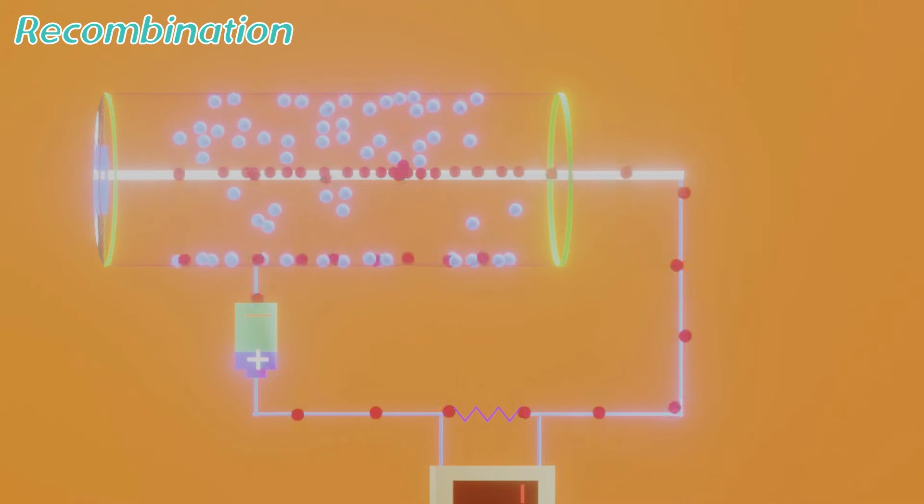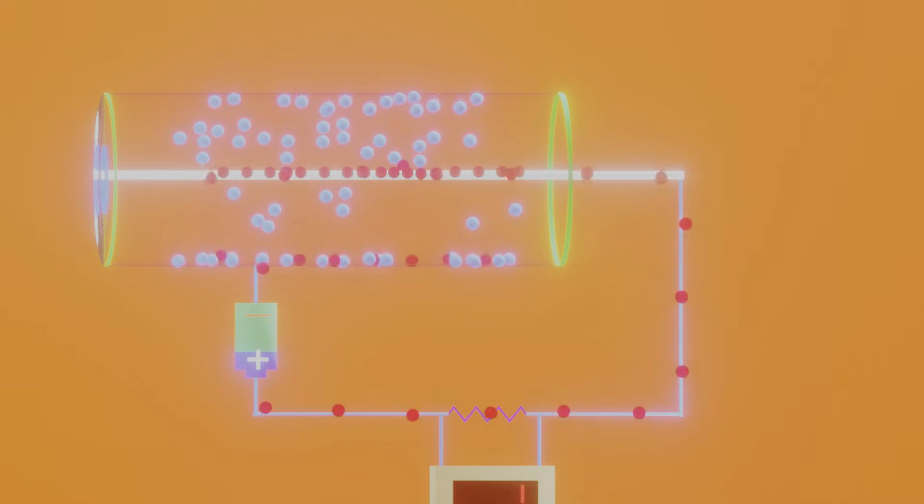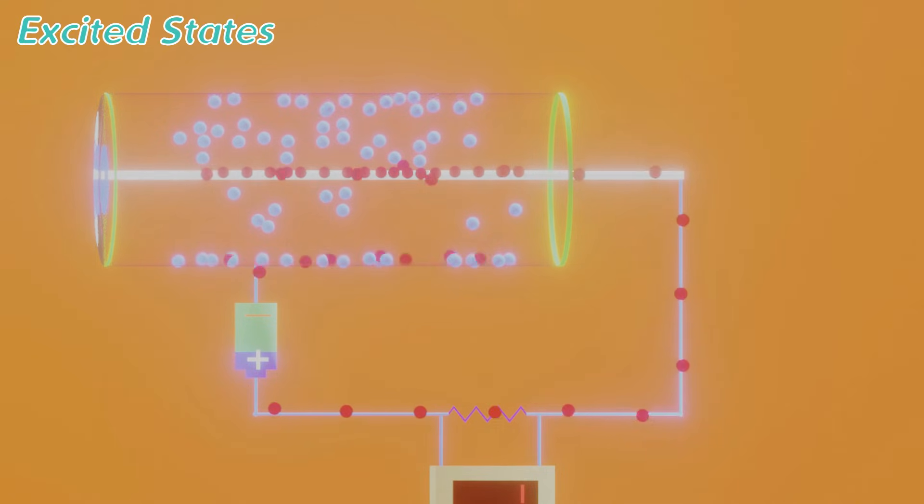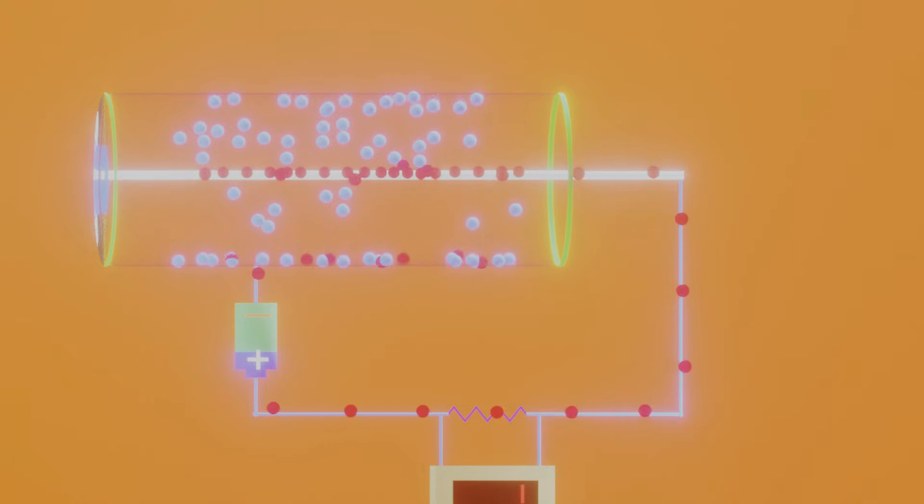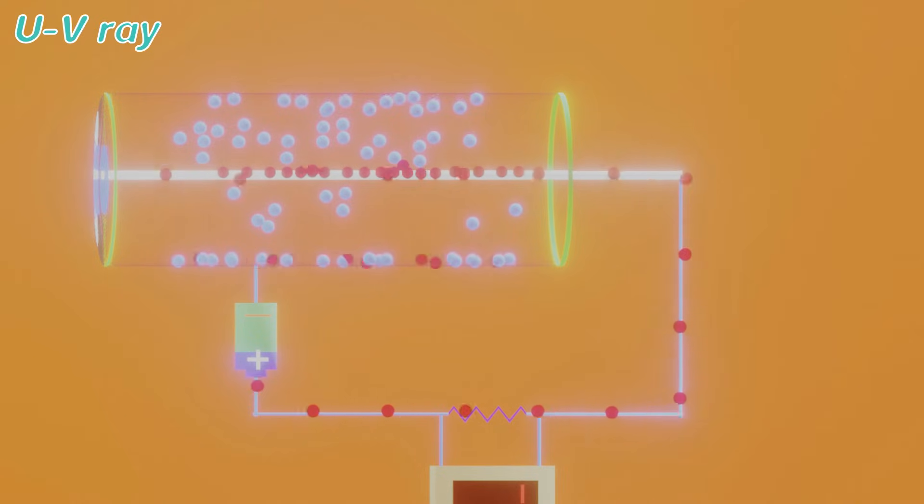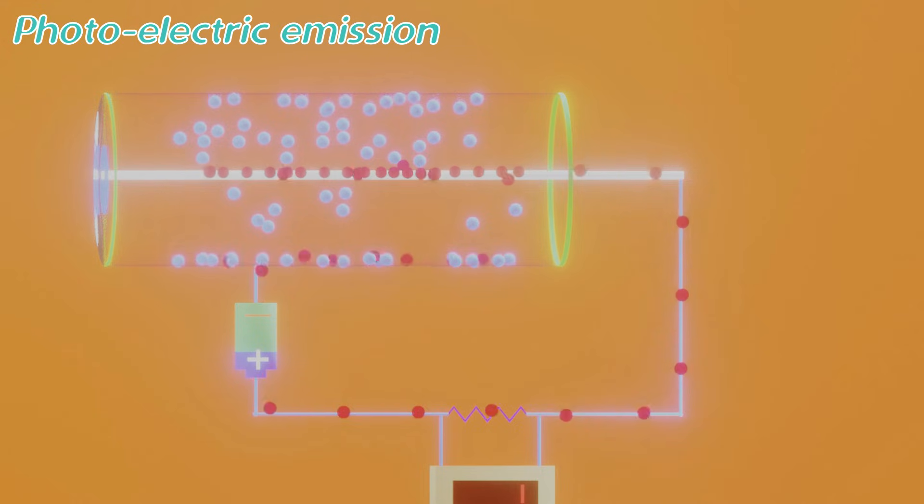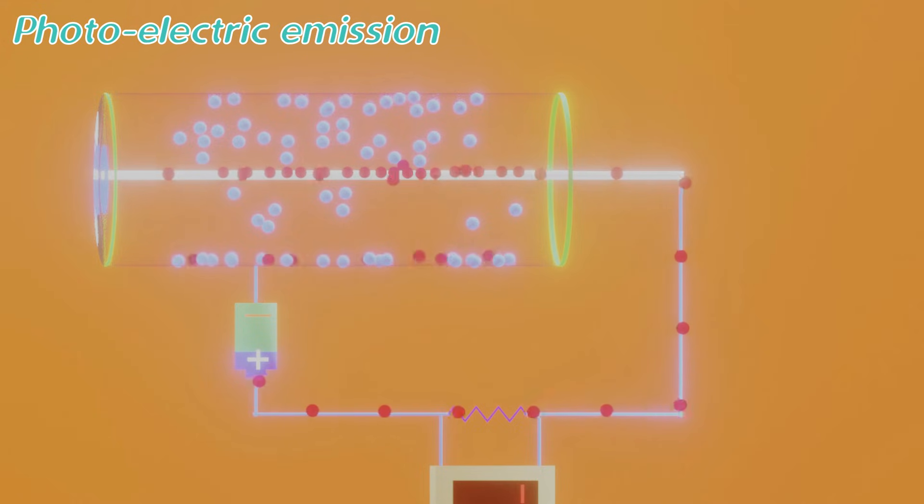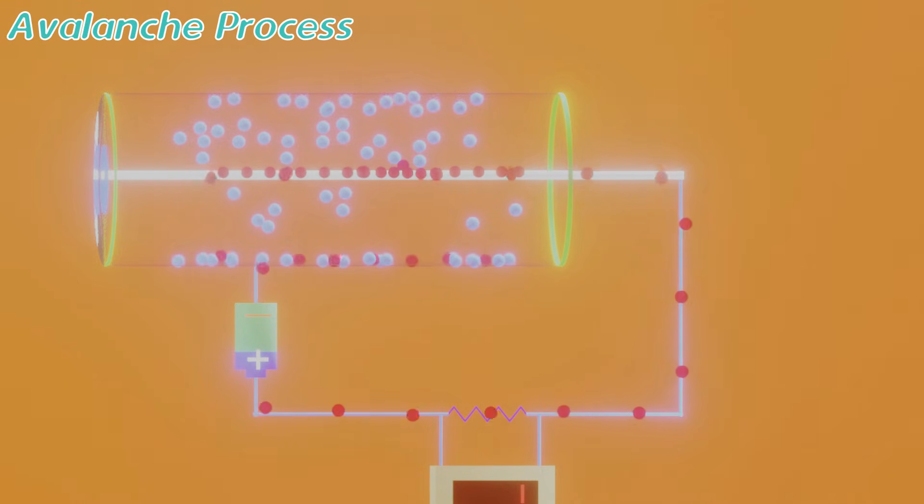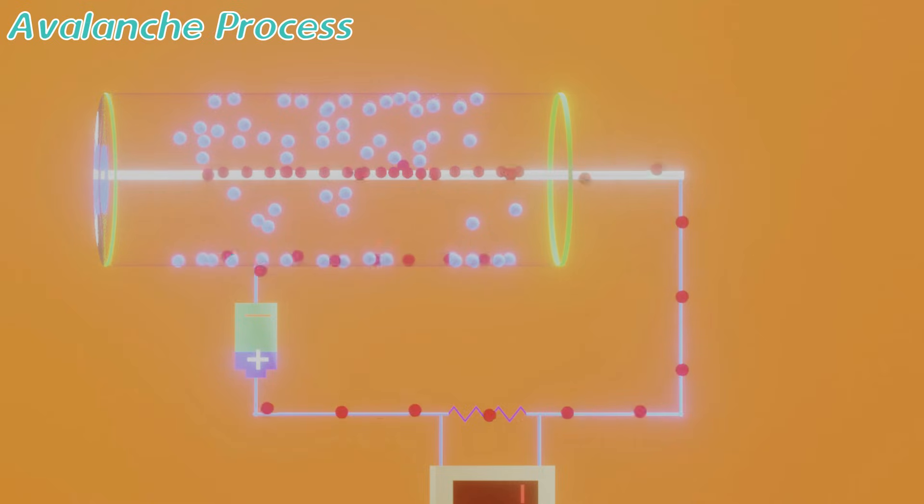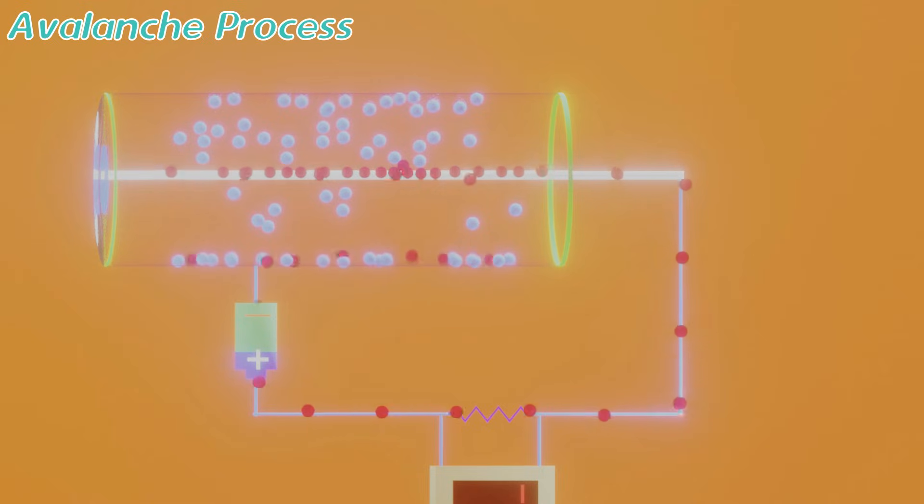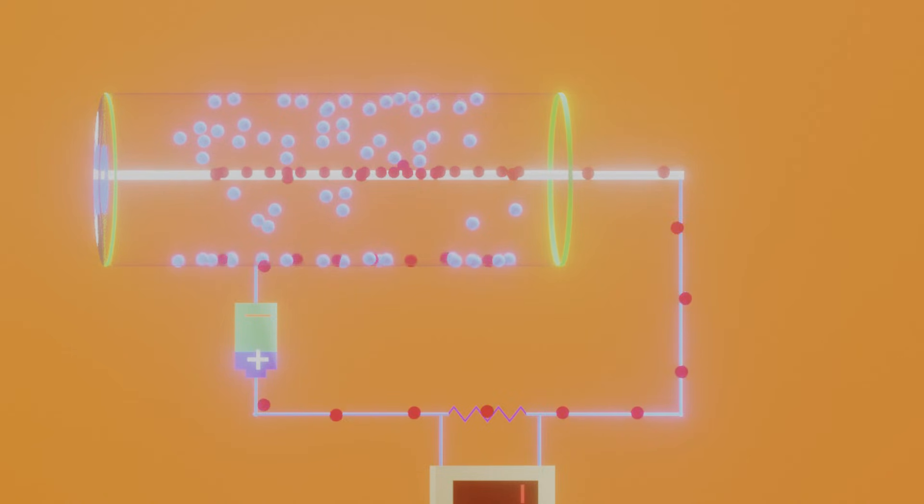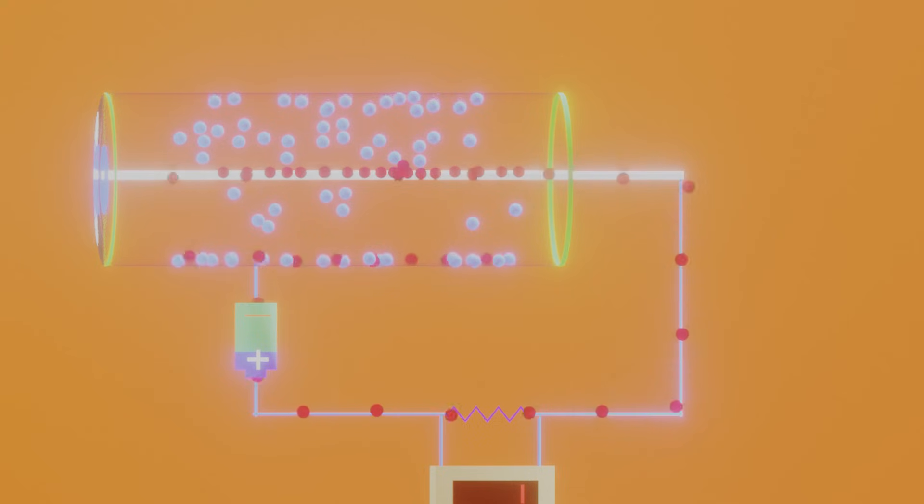When the recombination occurs, the resulting gas molecules are raised to excited states and then emit some radiation. And this emission contains some ultraviolet content, and it causes photoelectric emission from the cathode surface. And these photoelectrons initiate a fresh avalanche process. As a result we will get more counts which are not correct. So to get right counts, we must stop this photoemission.